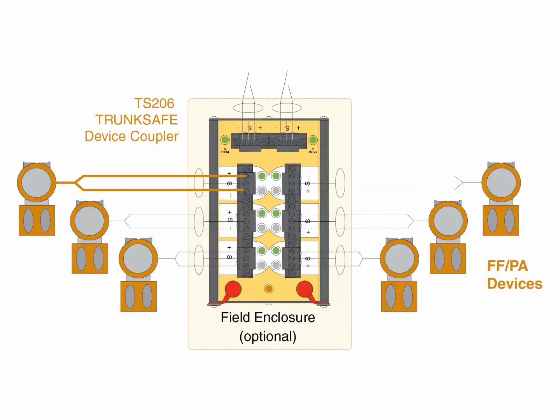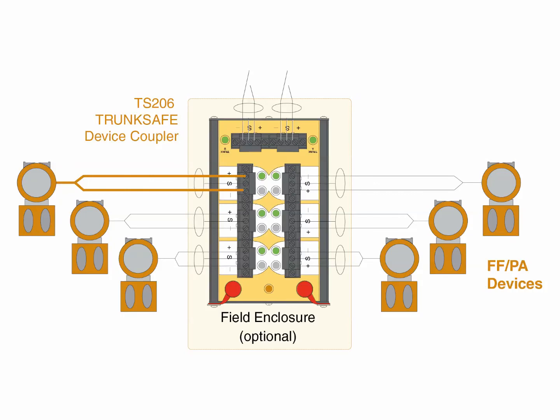Trunk Safe can also prevent segment failure caused by single-device faults. It uses a fold-back technique to automatically switch off any spur that attempts to draw more than 48 milliamps. A very small trickle current is used to monitor the circuit until the fault is removed. Once removed, the spur automatically returns to normal operations.